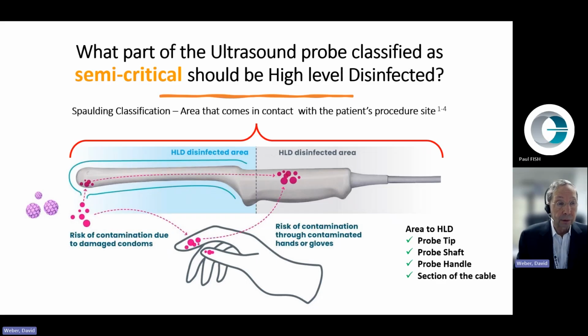We do recommend the use of condoms, but that doesn't mean that you can change the disinfection method. On the right, where the probe handle is that you're touching and which joins the cables, there is a risk of contamination through contaminated hands or gloves if you touch either the mucous membrane of the patient or the probe that's inserted itself. So areas for high-level disinfection include the probe tip, the probe shaft, the probe handle, and the section of cable that might be contacted by the gloved hands.